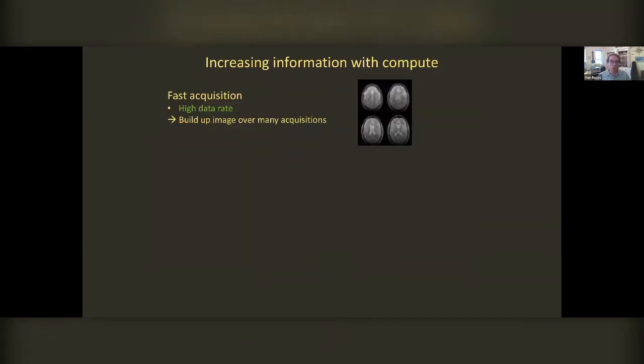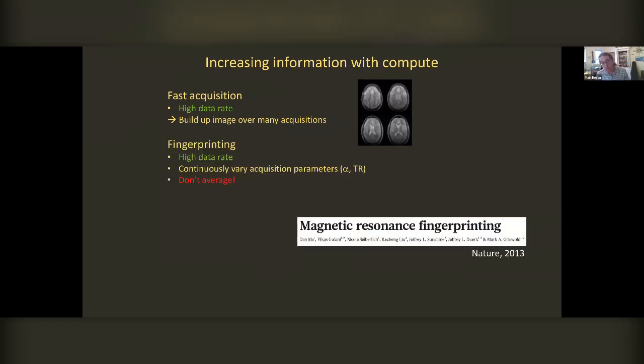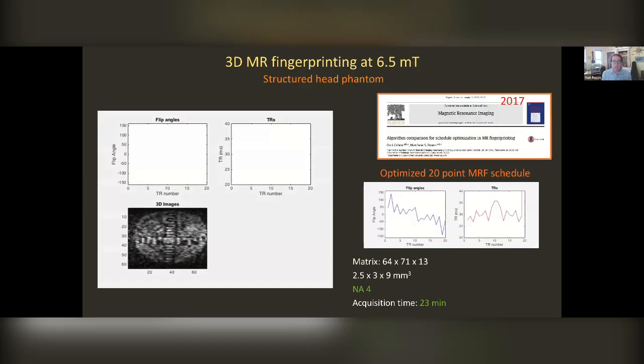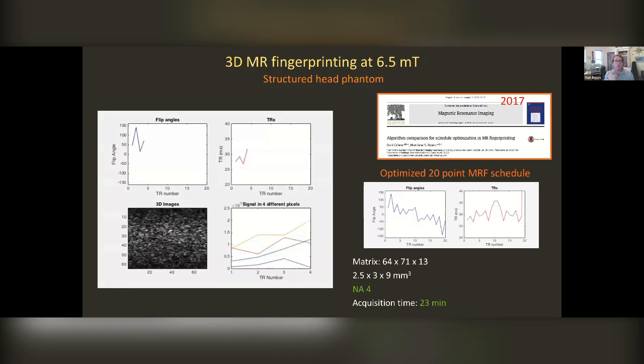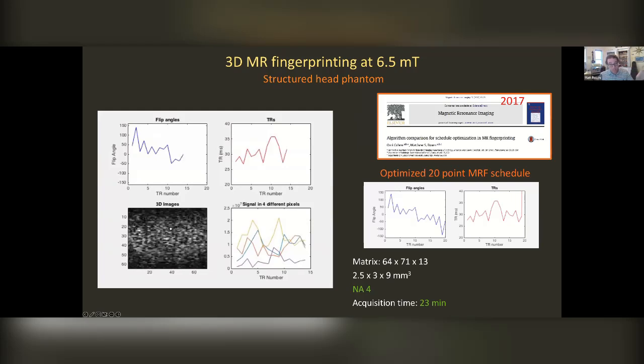Okay, so far, I've talked about ways that you can make pretty good images at ultra low field if you have a high data rate and you do signal averaging. Another approach to maintain a high data rate is to continuously dither your acquisition parameters, like your tip angle and your TRs. This comes out of the really pioneering work from Dan Ma and Mark Griswold of fingerprinting. And so this is what fingerprinting looks like at 6.5 millitesla in a structured phantom. You can see here on the left, we're changing the tip angle and the TR. The images are coming in. There actually is banding because the TRs are getting quite long.